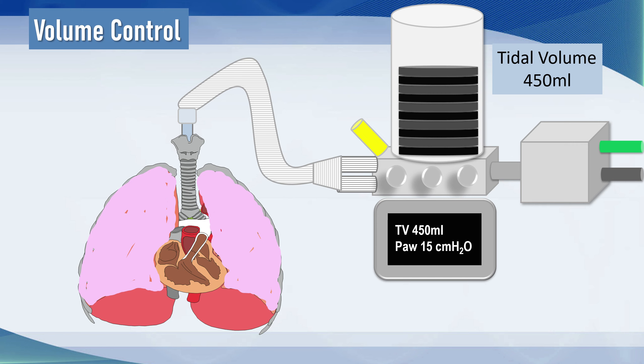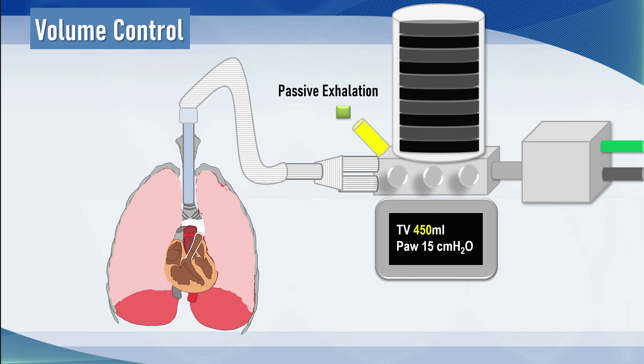The airway pressure being measured here is 15 centimetres of water. An important point about exhalation: when the ventilator cycles to exhalation, gas is released by elastic recoil back to the base lung volume — the functional residual capacity. Although we measure inspiratory airway pressure, the tidal volume is always measured in exhalation. That is the amount of gas ventilated out of the patient. We're looking to match the inhaled number with what comes out on the exhalation side, because what we set on the ventilator is the desired tidal volume, but if there are leaks in the system that may not be delivered.